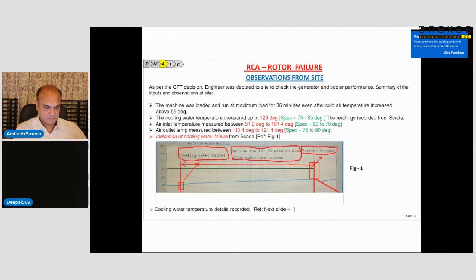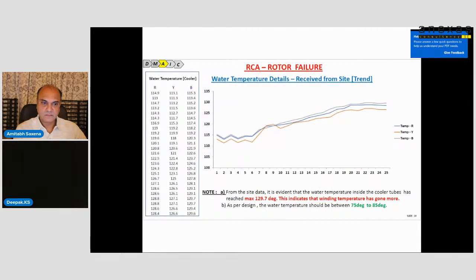So next, we recorded the cooling water temperature. Next slide. We can see the cooling water temperature details received from the site. Here I have put R, Y and B because it's a three-phase load, and it goes to the grid. From the site data, it is evident that the water temperature inside the cooler tubes reached a maximum of 129.7 degrees. This indicates that the winding temperature has gone higher. As per the design, the water temperature should be between 75 and 85 degrees. Next.